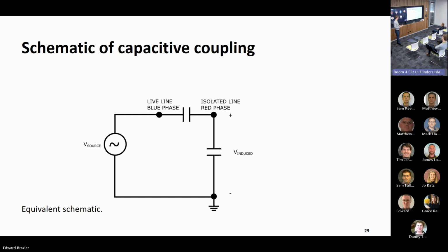Because the live line is energized, what we get is a capacitive voltage divider. That voltage divider determines the voltage on the isolated phase conductor, same for all three of the isolated phase conductors. This is the same phenomenon we looked at in that last diagram, just represented a different way.